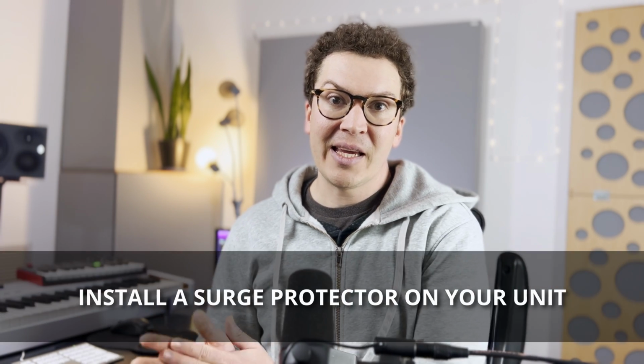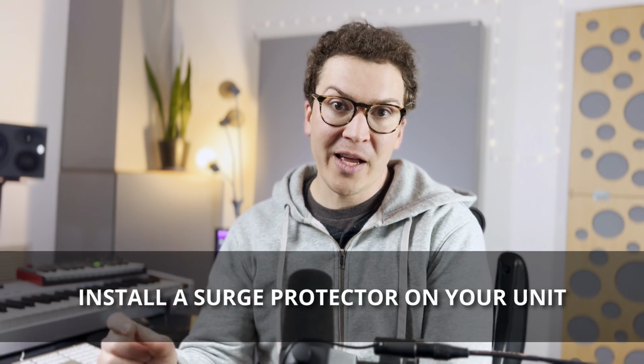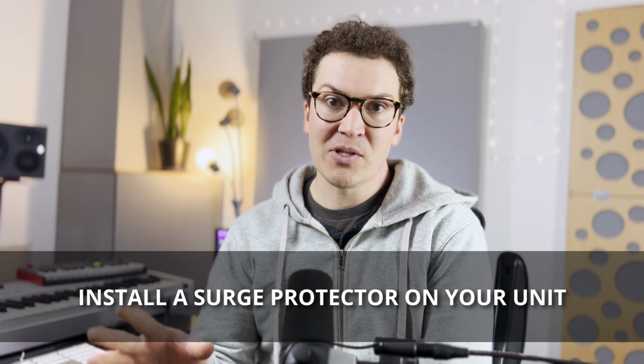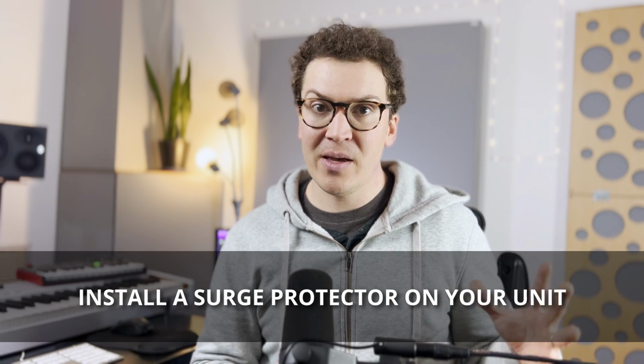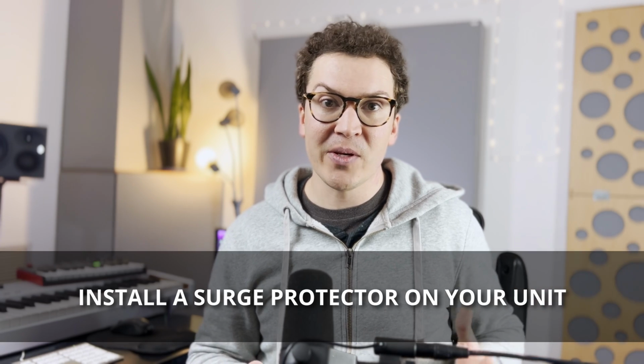Now, what I should have done — and this is the first lesson for you — is install a surge protector on the mini split itself. This is a surge protector. If you have any HVAC unit in your home, I highly recommend this: get an HVAC technician to install a surge protector on your unit, on the air handler, on the compressor, the condenser. That way, if there's a surge from your electric service, which we can't control, the surge protector takes the brunt of it instead of destroying your logic board or compressor.